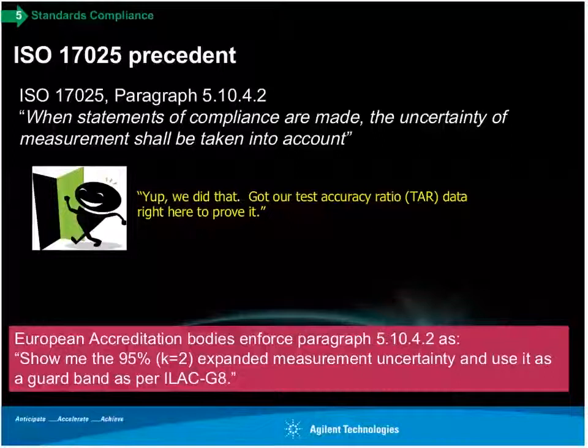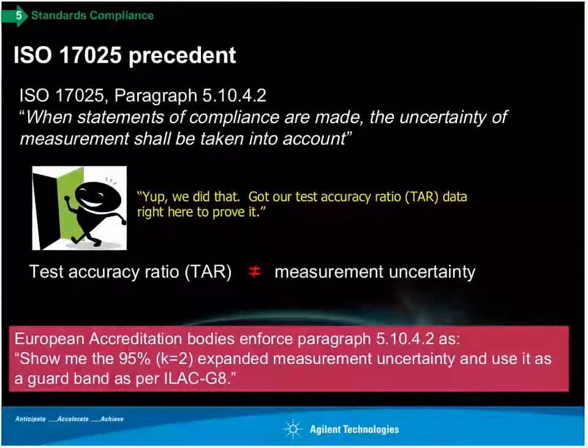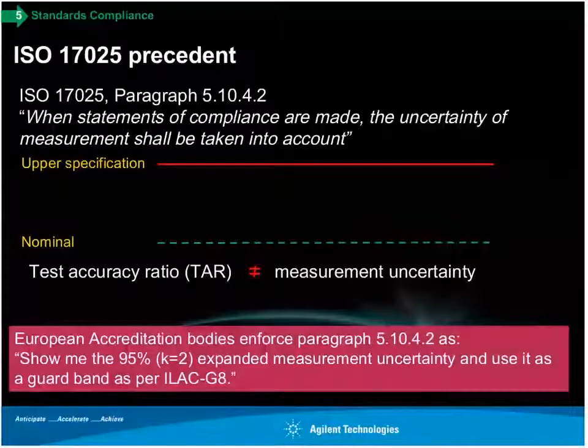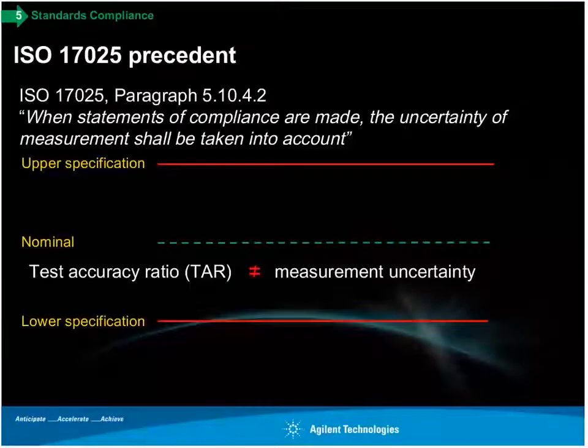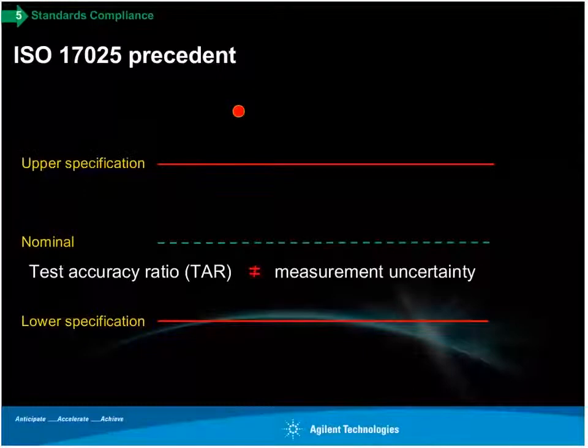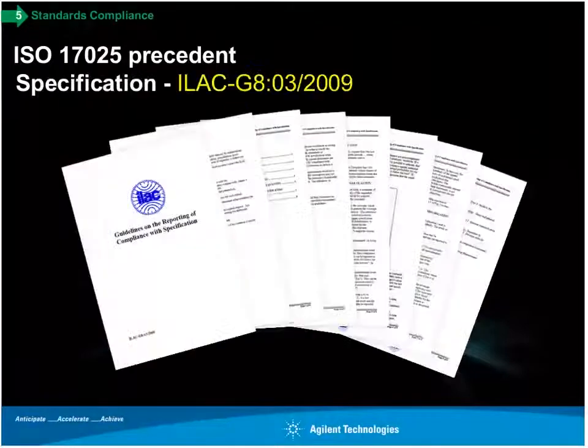That's why in Europe, most of the accreditation bodies enforce that paragraph as: show me the 95% expanded measurement uncertainty. And by the way, use ILAC G8 when you're reporting. If you want to claim that you meet 17025, that's generally how it is interpreted in Europe. Going back to this slide, what we're talking about is the yellow portion there, taking measurement uncertainty into account. Some of it is outside of the specification. How do you account for that? ILAC G8 gives clear guidance on that. Here it is again, and if you have interest, you can download it free. It's only about 10 pages long, if I recall.